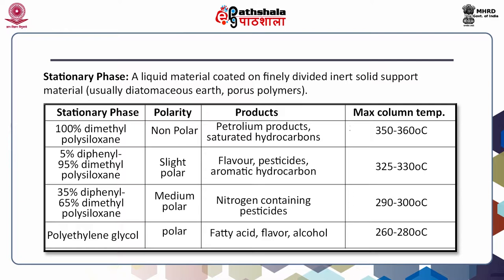For example, 100% dimethyl polysiloxane is a nonpolar stationary phase preferred for petroleum products and saturated hydrocarbons. Polyethylene glycol is a polar phase preferred for fatty acids, flavour, and alcohols. These stationary phases have different temperature maxima — they can remain stable up to a certain temperature and afterwards start degrading. The selection of stationary phase depends upon the type of material to be separated. A polar material will stick more to a polar stationary phase and elute at a later stage, and polar phase is generally more suitable for compounds with different functional groups but similar boiling points.